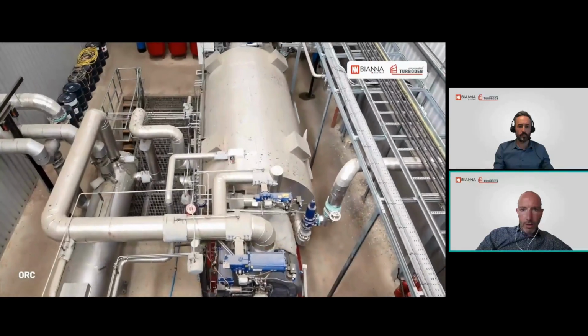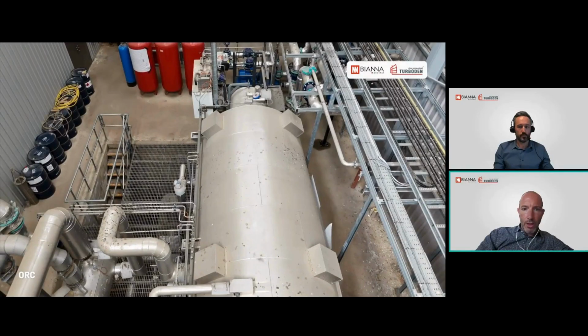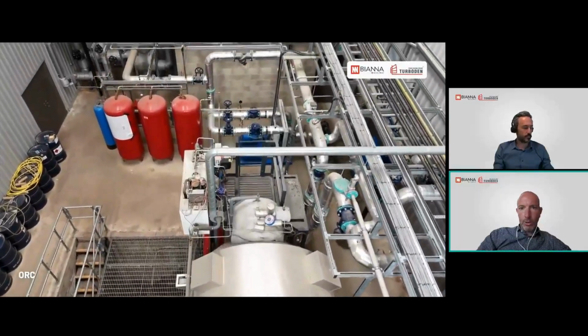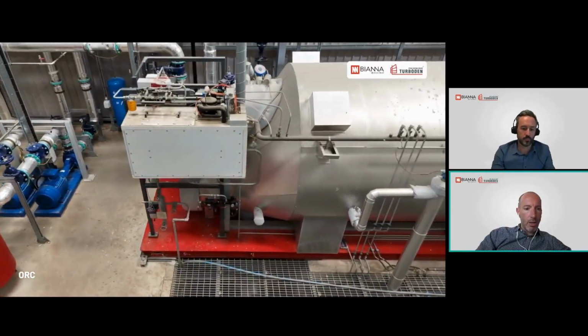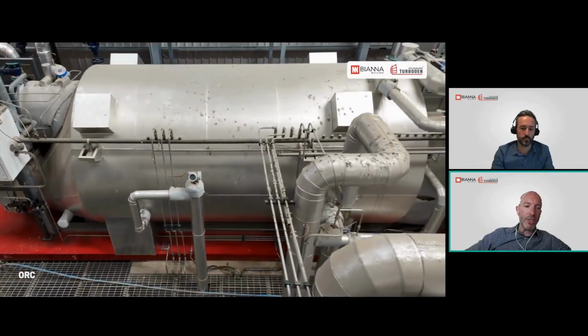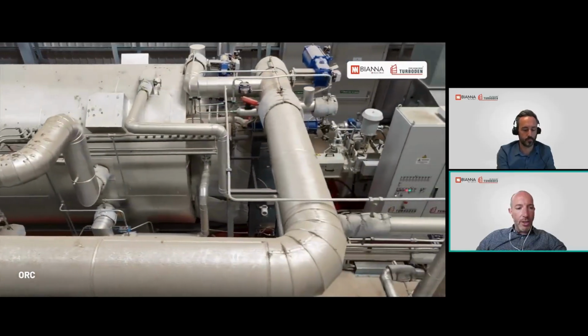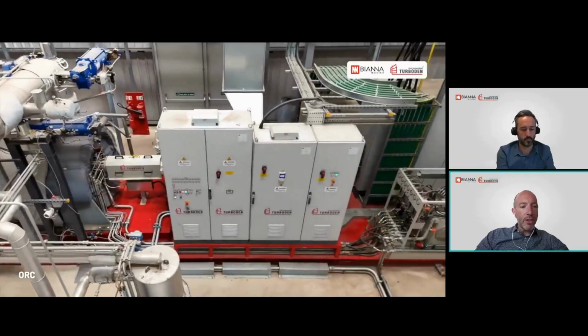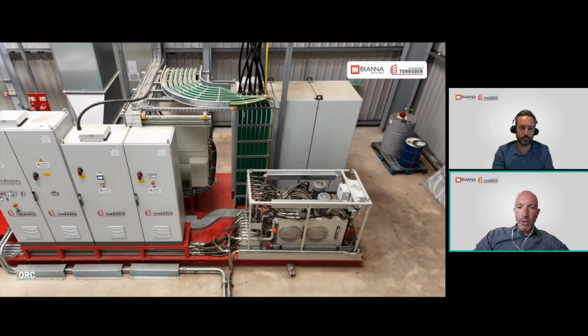Just on the side of the condenser, you see there is a pump. The pump is located in a pit around 4 meters deep, that you can spot covered by a grating floor and an access stair, for maintenance. So it's a very compact and simple installation. The key feature is that the whole system operates at low pressure, which adds to the safety and simplicity of the design. To streamline installation on site, all main components are pre-mounted on skids. You see this red frame here, where all the components are mounted, as well as the electrical panels that are pre-cabled in our workshop.